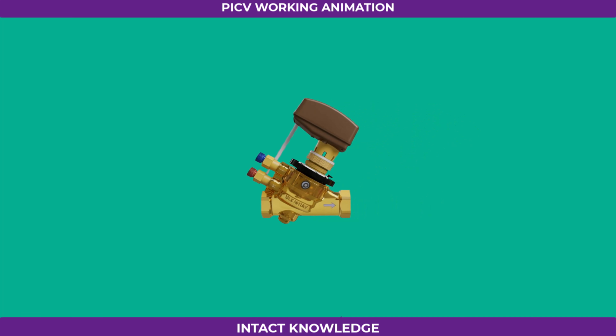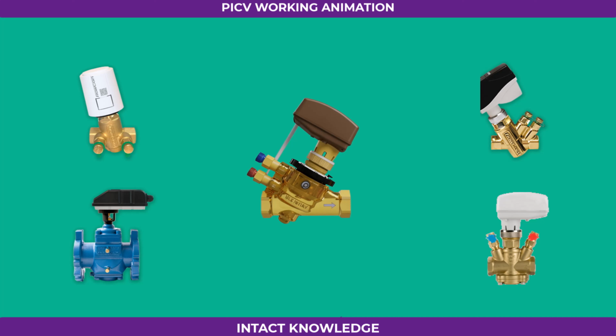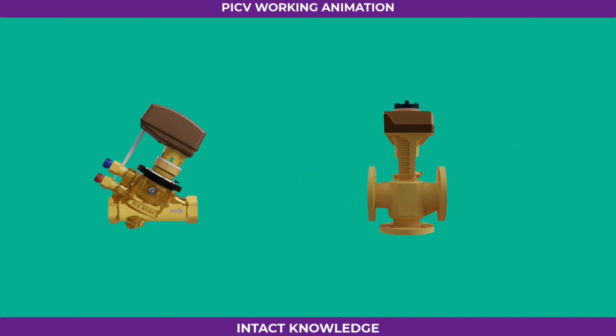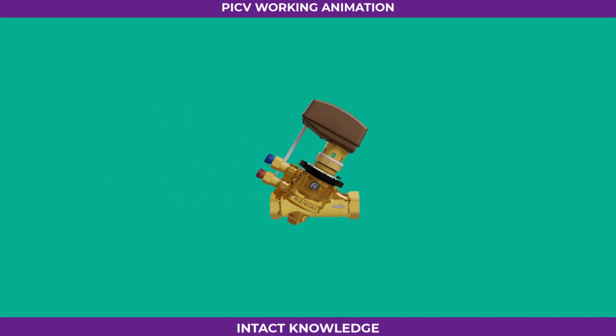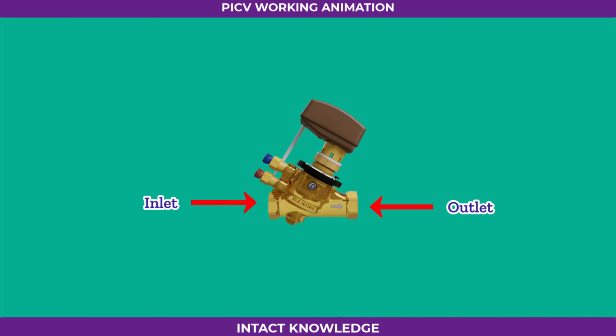Now, let's understand how a PICV actually operates. You'll find many different PICV designs in the field, but the working principle is always the same. A PICV behaves much like a standard valve. We encounter two main valve types, the two-way valve and the three-way valve. Let's look at the key parts that make up a PICV. Here's the inlet, where water enters the valve, and here's the outlet, where it exits. Water flows through the inlet and moves out from the outlet after regulation.